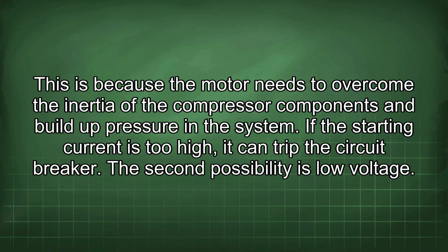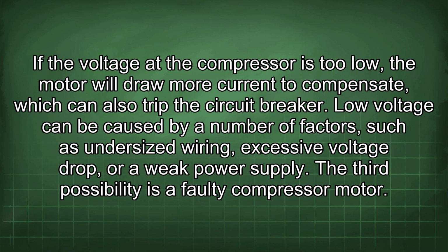If the starting current is too high, it can trip the circuit breaker. The second possibility is low voltage. If the voltage at the compressor is too low, the motor will draw more current to compensate, which can also trip the circuit breaker. Low voltage can be caused by a number of factors, such as undersized wiring, excessive voltage drop, or a weak power supply.